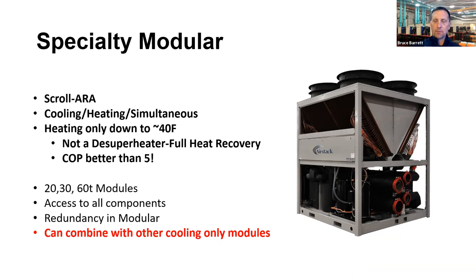Last week when we talked electrification, I certainly can't not reiterate our specialty modular chiller, our scroll ARA, the ability of this air-cooled chiller to do both cooling, heating, and simultaneous heating and cooling. This can be packaged with our ASP modular chiller. So if you've got a simultaneous load or a small heating load where your cooling load is much greater capacity, you can pair this machine with standard cooling only machines.